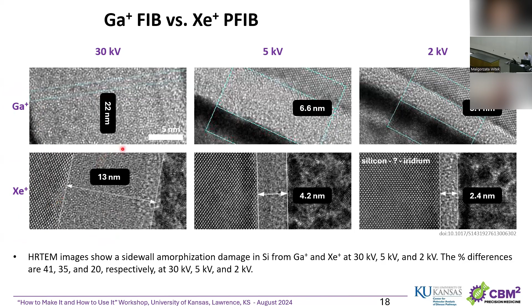So when you use the same acceleration voltage, you can see a large amorphous area when you use gallium ion compared to xenon ion. So what does it mean? It means that if in your application this implantation or damage of the surface structure is a very big issue, then it's better not to use gallium, but xenon instead. Depending on your application, you have to select a different ion source to accommodate your device needs. So I think that's all for the first part of my talk. We're going to take a 10 minute break and come back for the imprinting. Okay.